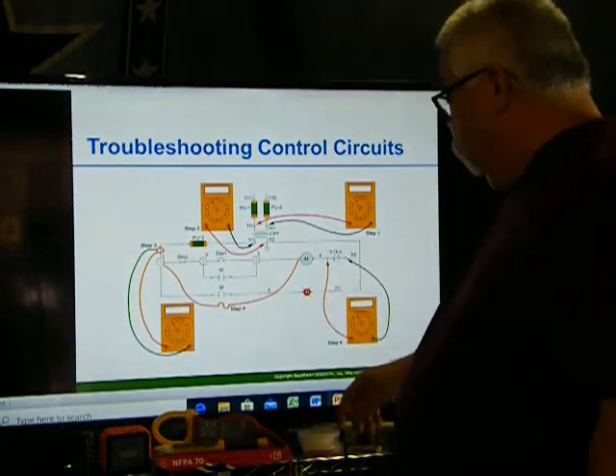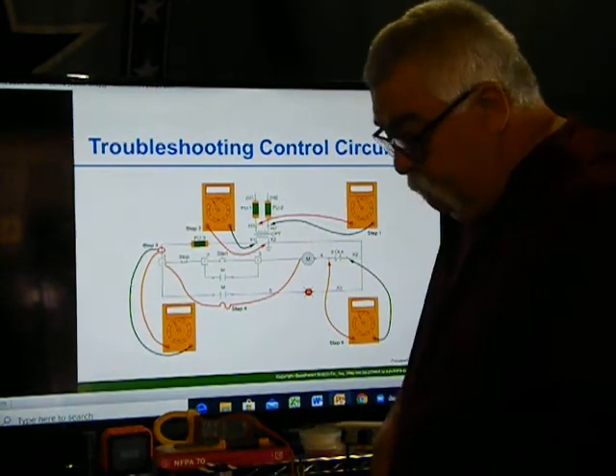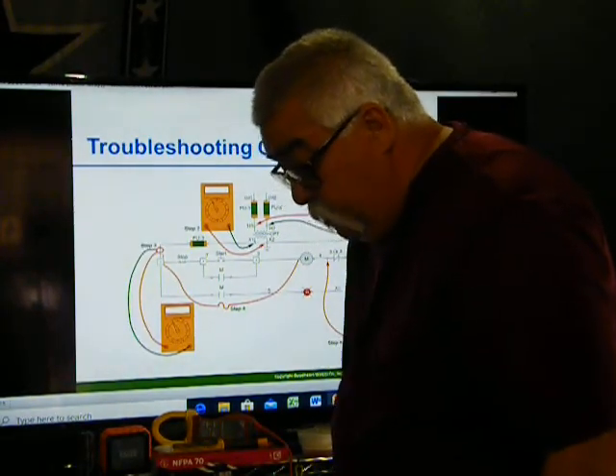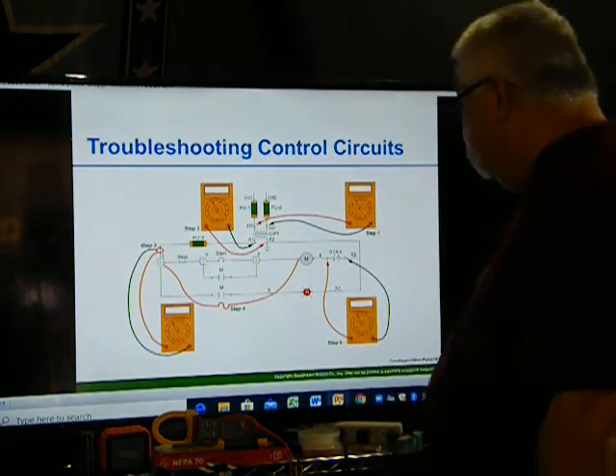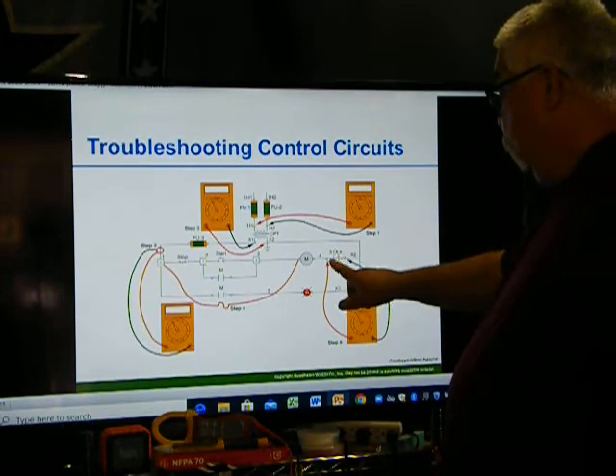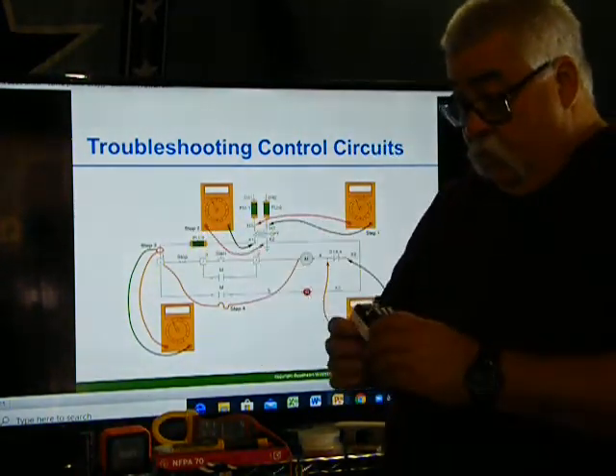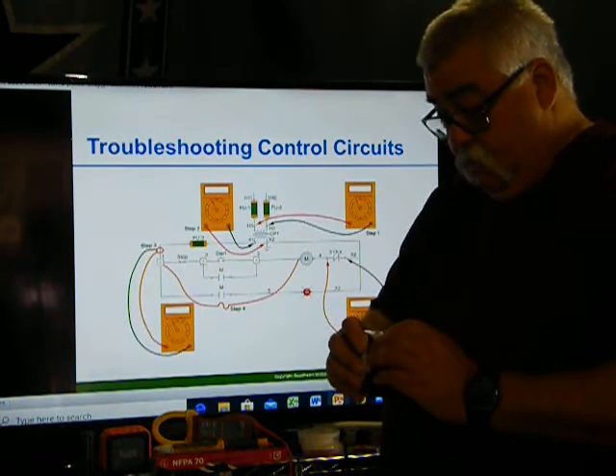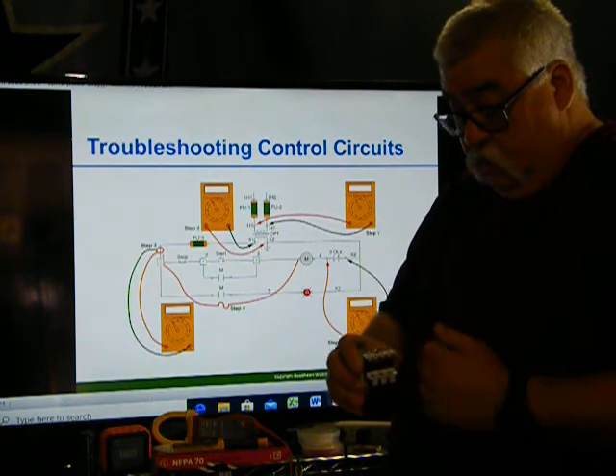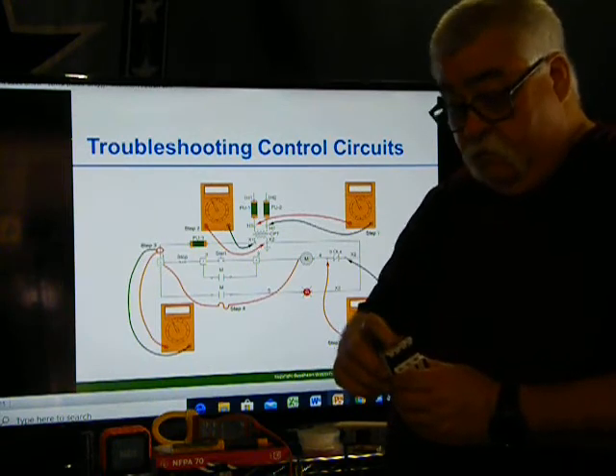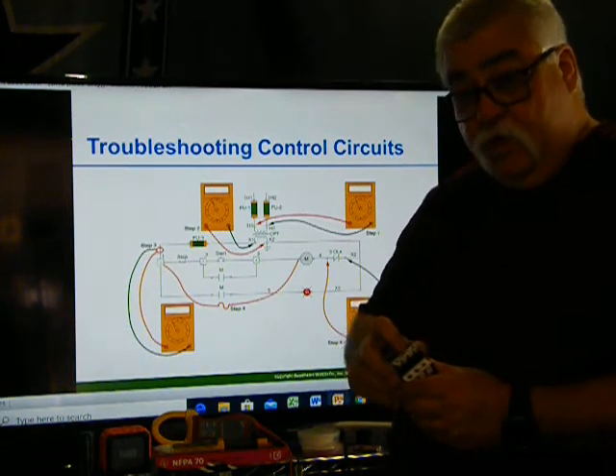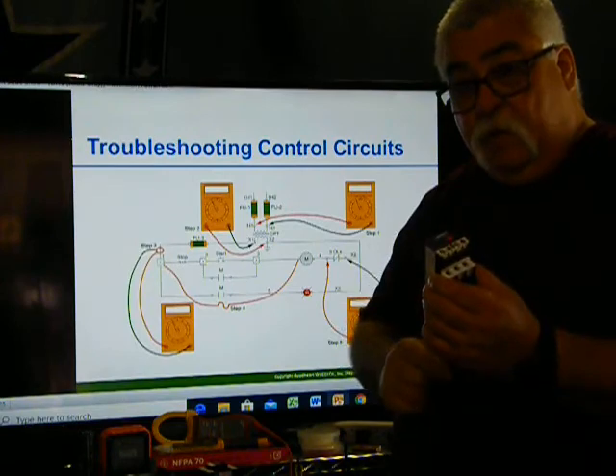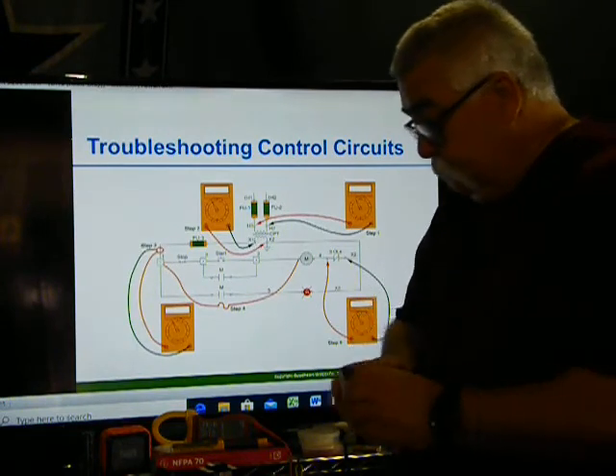So you have to check everywhere else. And then step 5 is the motor does not start with the jumpers installed. Check the voltage across the overloads with the jumper still in place. So here I have another, this is my overloads. So I'm going to have a wire in. So this is normally open, normally closed. So this is closing. If this is not closing, if I hit the reset, this is not closing, then this may be the problem.